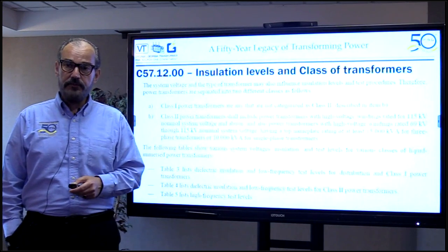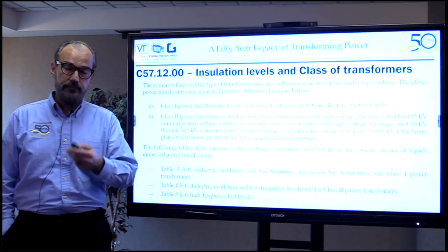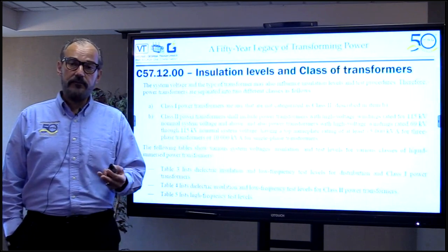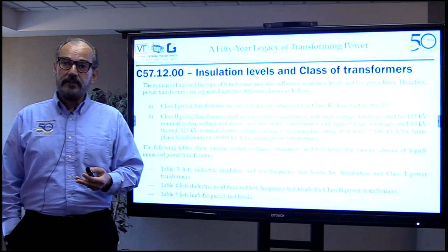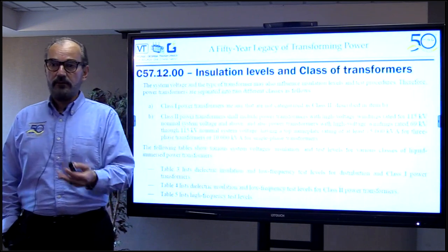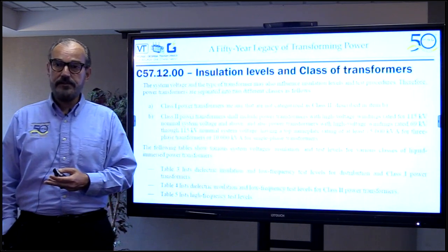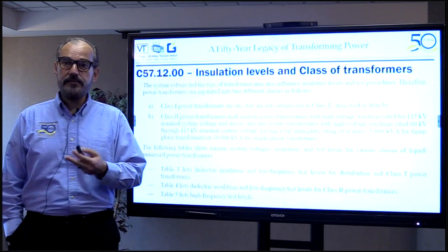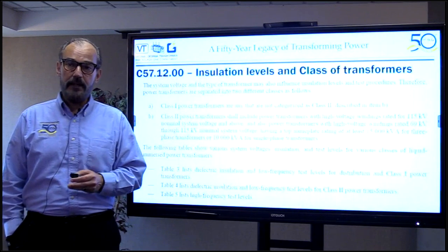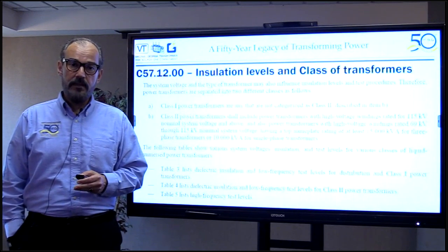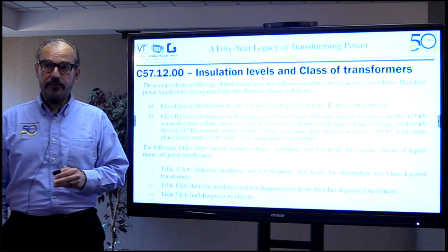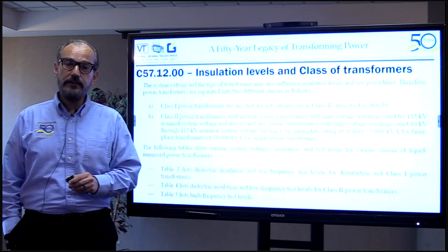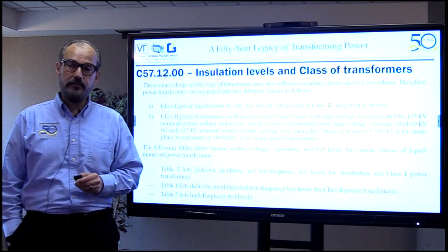The class of the transformer is referenced in Tables 3, 4, and 5 of the standard, which define the low-frequency test levels, dielectric insulation levels, and high-frequency test levels per class. This is why I thought it was important to start this presentation by clearly explaining the transformer classes.